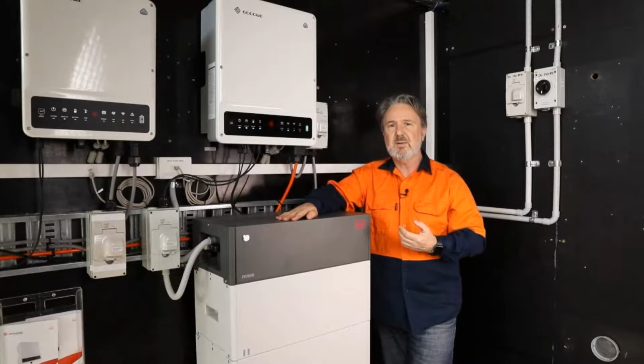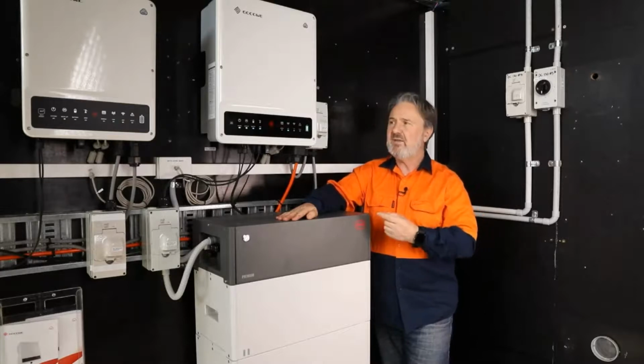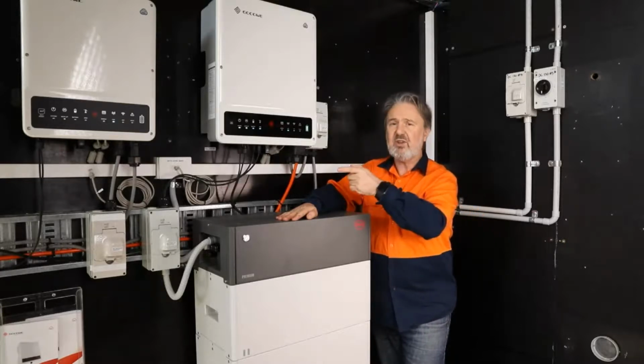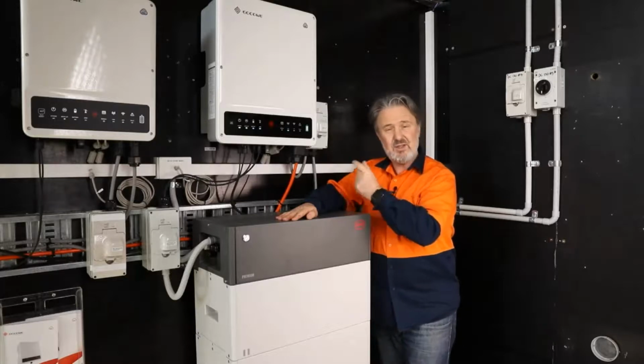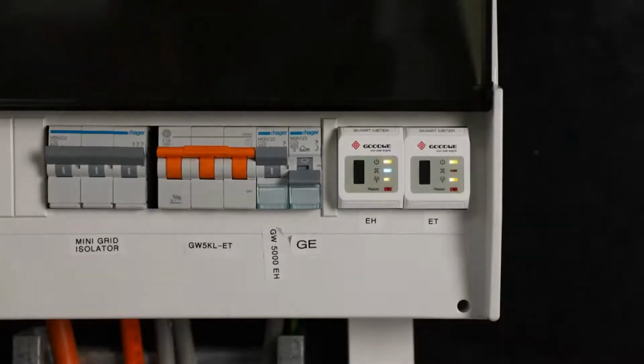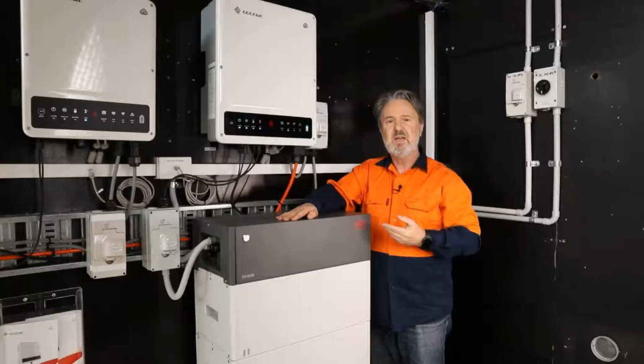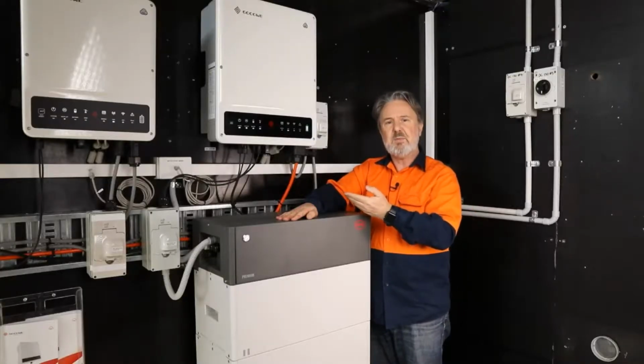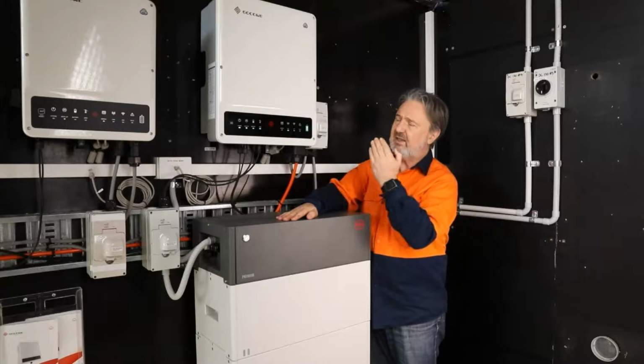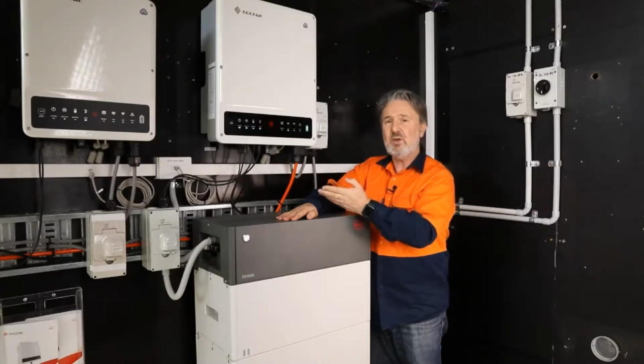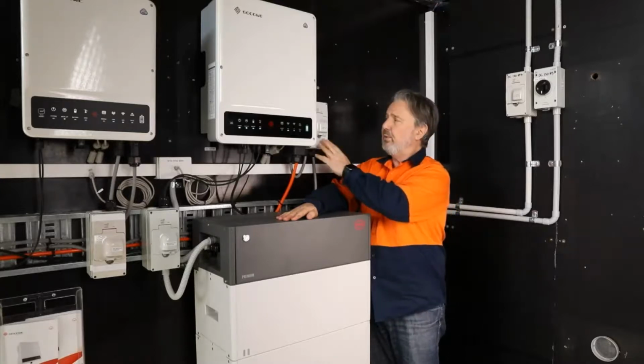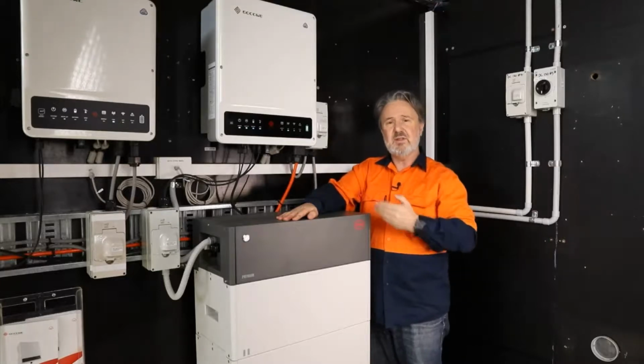In hybrid mode, these have an external CT, both units, and a meter. The meter's great - it's only 2 modules wide, with a little display with some LEDs on it, so it tells you there's communication occurring, which really speeds up fault finding if you're trying to work out why the meter's not reading. Both of these have UPS backup functionality - there's less than a 10 millisecond transfer when the grid fails, so the backup port is hardly interrupted, 10 milliseconds or less.